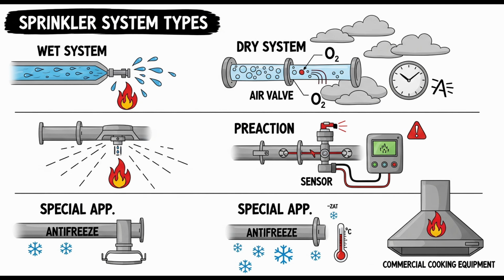Subdivision is also required if the system is large or covers multiple fire areas, similar to other systems. Right. If there are more than 275 sprinklers in a single fire area, the system must be divided into sections of 275 sprinklers, or fewer, using check valves. If the system covers more than one fire area or story, no more than 600 sprinklers can be supplied through any single check valve. Manageable sections. And each section needs draining capability. Yes, a 1 1/4-inch drain is required on the system side of each check valve, plus a standard dry pipe auxiliary drain for low points. These drains must be located in heated areas or heated cabinets to prevent them from freezing, just like the main valve room. Critical for maintenance in potentially very cold, exposed environments.